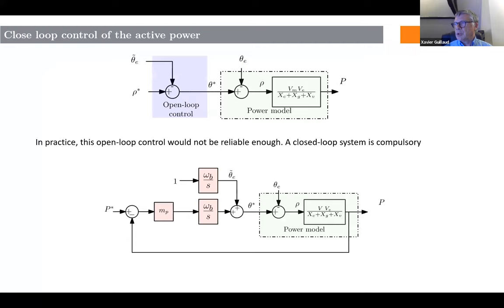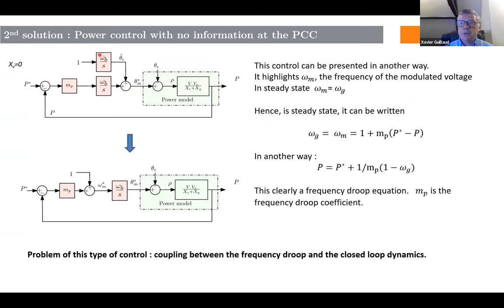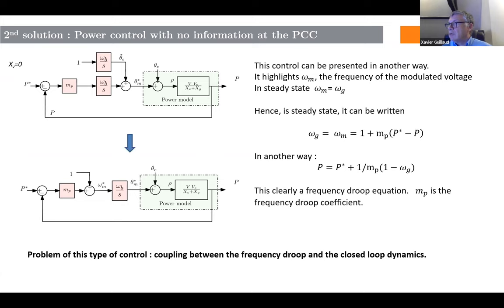Now it is time to close the loop, because it is not possible to control the system with such a simple open-loop control. Starting from this model, if I want to control the active power the very basic solution is to add an integrator. Modifying this scheme slightly gives a very well-known droop control. This is the way I explain the origin of droop control, really starting from scratch from the system model. We can add a filter if desired, but this is the very basic scheme of droop control.